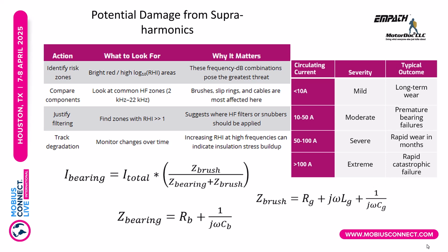So what does that mean? When we get into the red zones and everything else, we need to start thinking about filters. At that range, we can probably get away with a shaft brush, but not really for the higher frequency noise. The reason for that, and yes, complicated formulas, but let's talk about the bearing. Bearing, because of the lubrication, is a capacitor. So as I increase that frequency, its resistance drops. Now the brush, the shunt and the material itself, that's an inductor, and then the material is a capacitance. So as I increase frequency, the shunt in particular is going to go up in resistance. And normally when I hit about 10 kilohertz, give or take, I start seeing that shoot right up, while the bearing is shooting down. They cross each other.